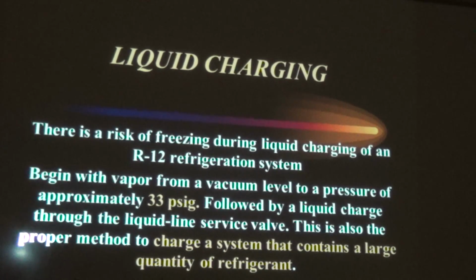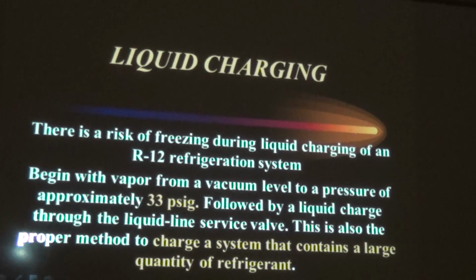And the reason we're talking about liquid charging is that Type 2 equipment usually is the equipment that's going to have double-digit weight of refrigerant, and you want to charge as a liquid so you're not spending your life doing this.